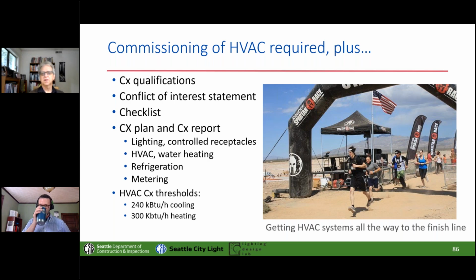That's a lot - so you've got to commission your HVAC system. It's amazing how much resistance I've had to commissioning in the past before it was required. But this is about getting your money's worth out of all the investment in these fancy systems we're requiring, by having a disinterested party come in and see if it actually works, if it does all the things it's supposed to do. It's amazing how frequently it doesn't. So you can fix those issues and then hand over a working system to people.